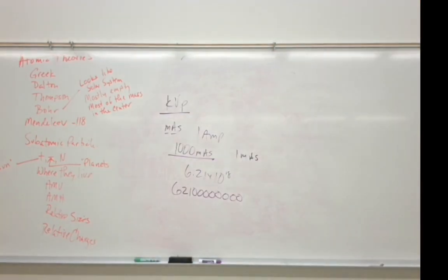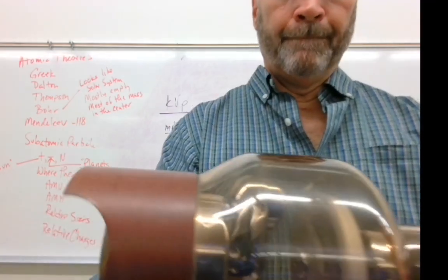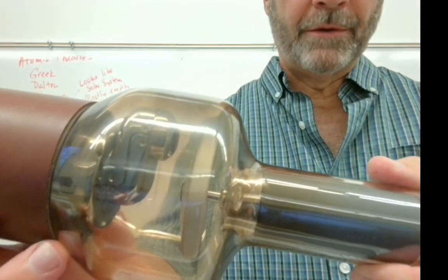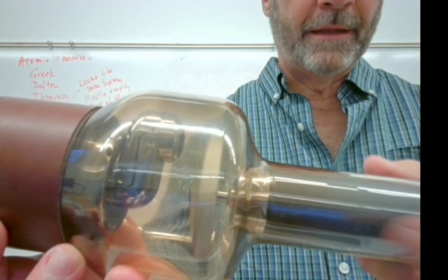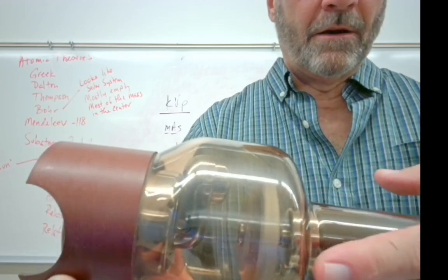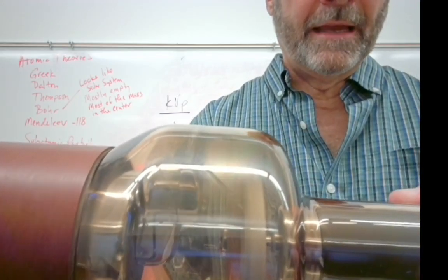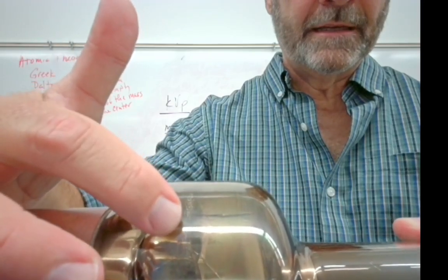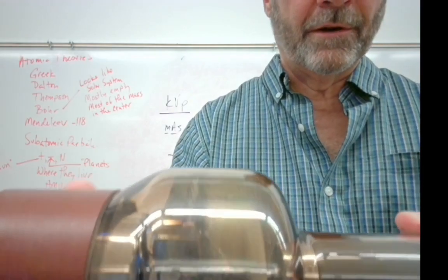And then our X-ray tube itself, you can see the components of it. And we've got to be real careful with this one because it's already broken. It's got cracks in it. But you can see the individual components. So we've got the entire rotor assembly at this end of the X-ray tube. This entire black thing spins along with the disc that you see in there. So you see the distance between the cathode and the anode is not very far. We create our thermionic emissions on this and we send them across the X-ray tube to interact on the face of the target.